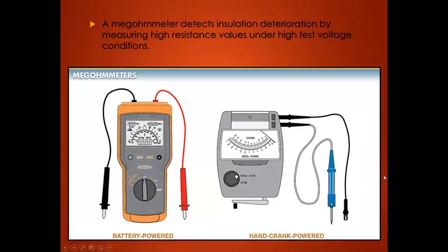That insulation is supposed to protect, say, the outer frame of a motor or the other windings in a motor from electrical induction, I guess you could say. So this tests the insulation integrity and makes sure that your windings and your insulation are good.